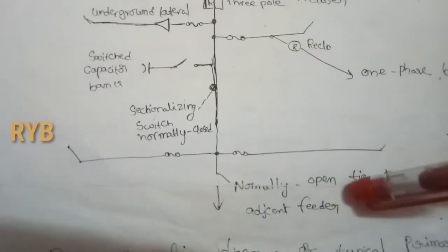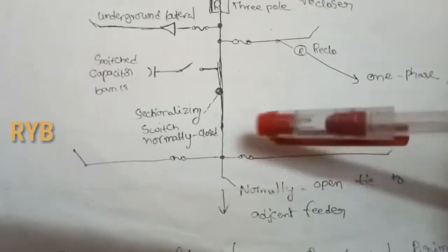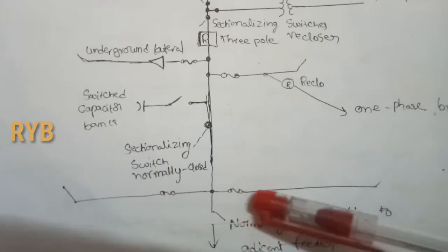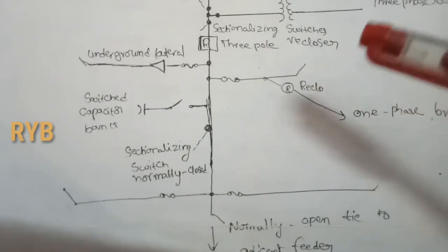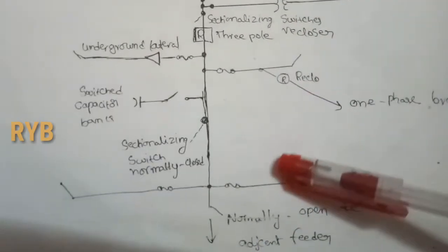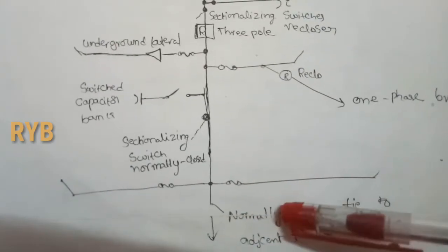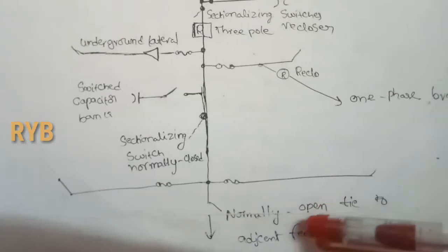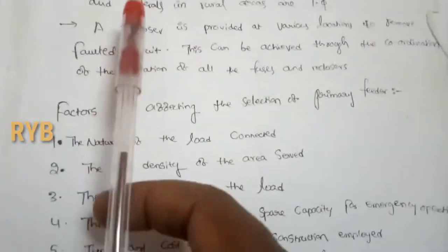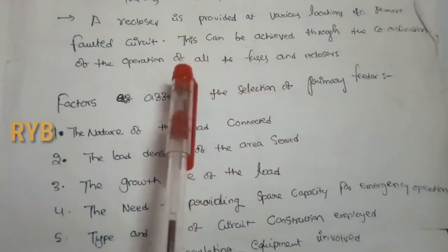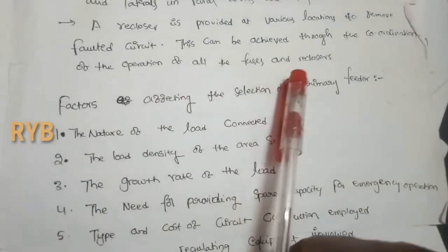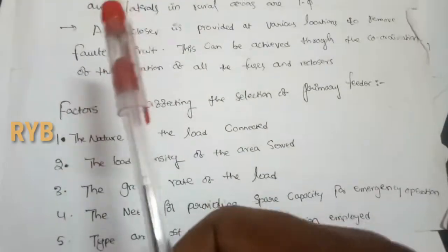A tie switch is a switch that connects an adjacent feeder from another feeder; it is normally open. Sectionalizing switches are normally closed. Tie switches are used to connect bus couplers and for emergency feeder connections — they are normally open under regular operating conditions. A recloser is provided at various locations to remove the faulted section, and this is achieved through coordination of the operation of all fuses and reclosers.